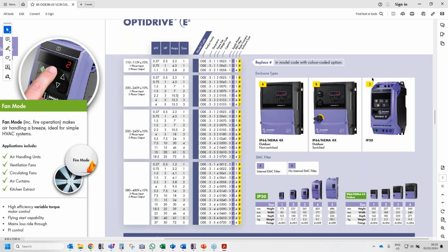So I have another question here. What about if we have a single phase voltage in the supply, in the source, and we have a three-phase motor? Well, for single phase 200 volt or 200 to 240 volt, we have drives which can take a single phase input and give you a three-phase output. So that goes up to 15.3 amps. So that's no problems at all. We have that possibility already.